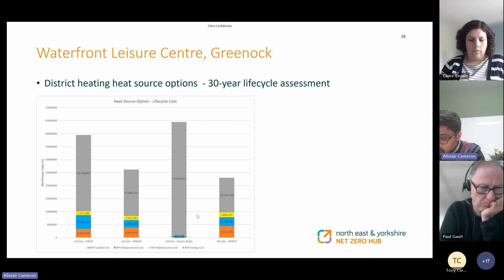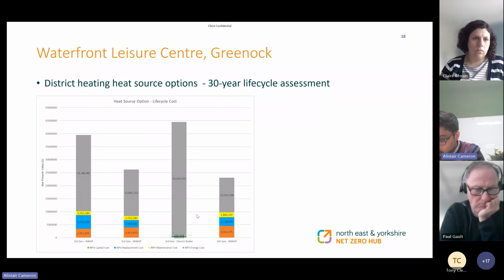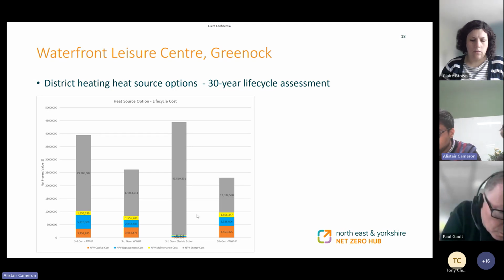And then number 2 in the performance was the water source heat pump. So that's taking energy from the Clyde and upgrading that energy to useful heat, which is then circulated to each of the buildings associated with the network. And that had slightly higher capital costs because ultimately water source heat pumps are generally more expensive than air source when you account for the water connection to the river. Slightly less replacement costs, very similar maintenance costs, but the operational running costs go down quite significantly. So it goes from 29 million to 17 million. So that's quite a big reduction.